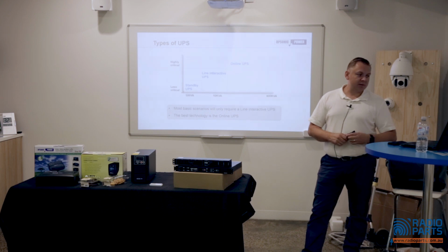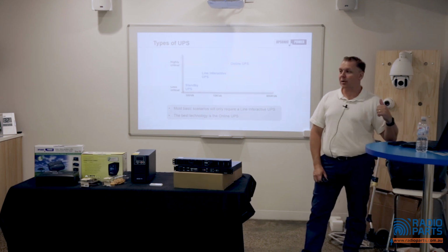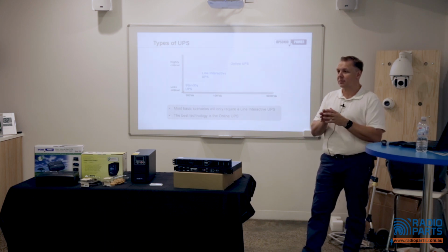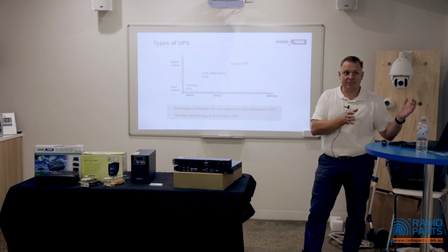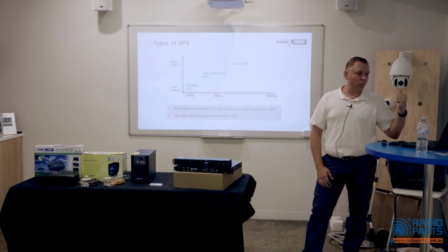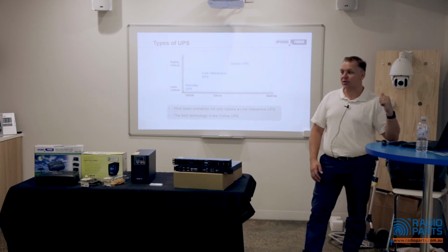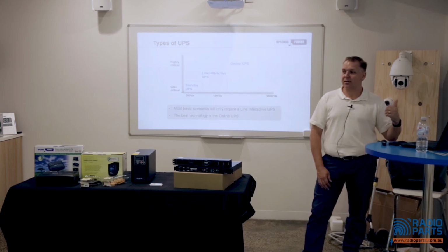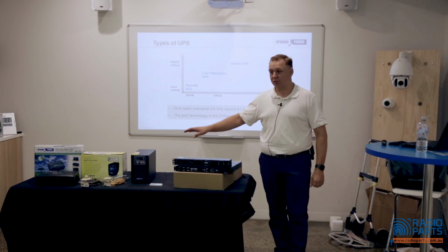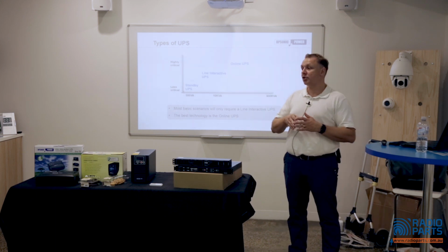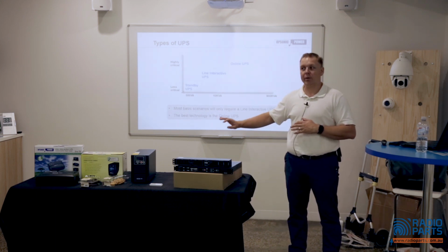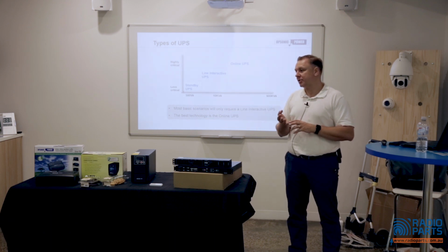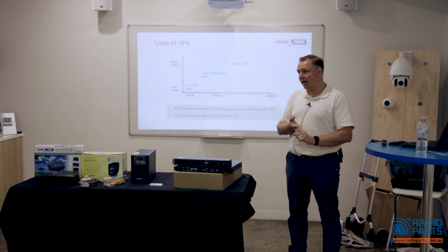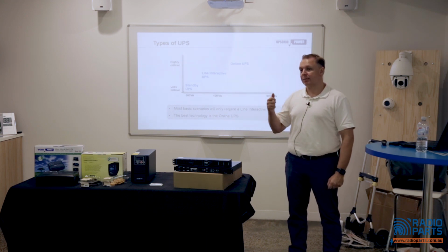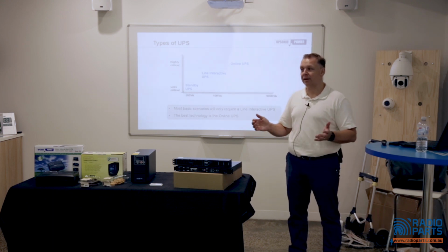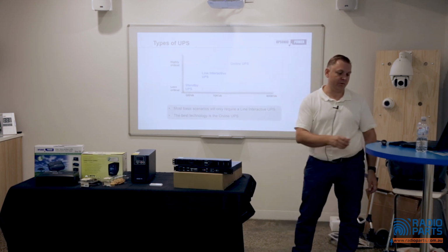With our types of UPS, they have different applications, obviously. Our standby UPS are typically smaller and cheaper to build because with the electronics we'll get into in a second, there are just fewer of them. Typically they will be a smaller unit on a less critical load. If the load is critical, we'd definitely steer towards the dual conversion units. And once we go to hardwired systems, it's dual conversion all the way. The other sizing considerations to keep in mind: up to 2 kVA, we're still at a 10 amp plug top. We then step to 3 kVA, which is a 15 amp plug top. Anything bigger than that is hardwired, so it means an electrician to install it and all of those things.